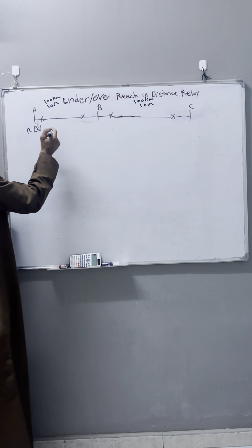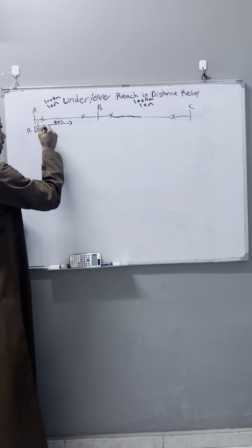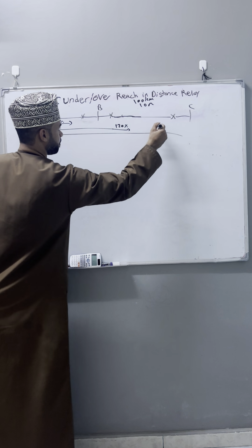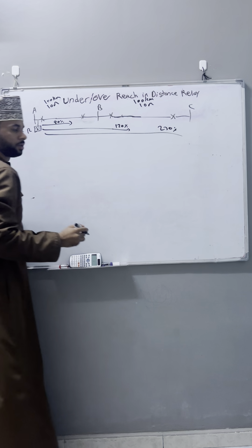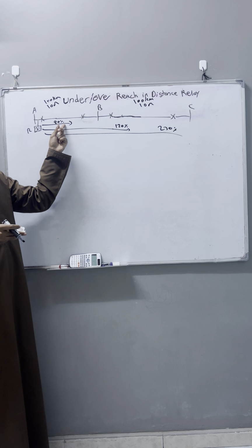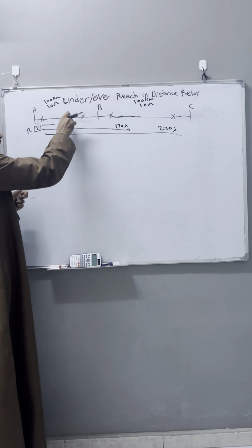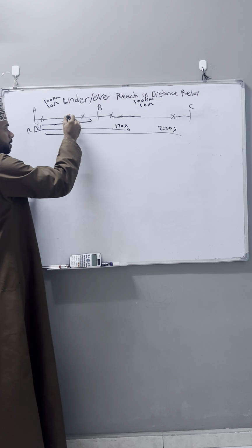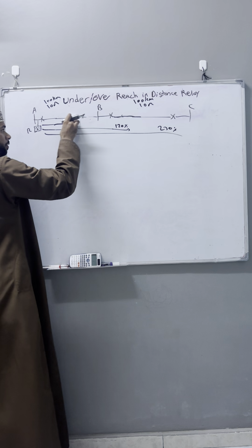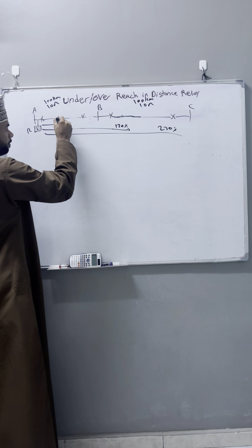And this is our distance protection relay, and you know the distance relay: zone 1 protects 80 or 85 percent, zone 2 covers 120 percent, and zone 3 protects 220 percent. Also we'll see why we need zone 1 to protect only 80 or 85 percent. Why don't we make zone 1 protect 100 percent? We'll see why we don't make it 100 percent, and we make it up to 80 or 85 percent.